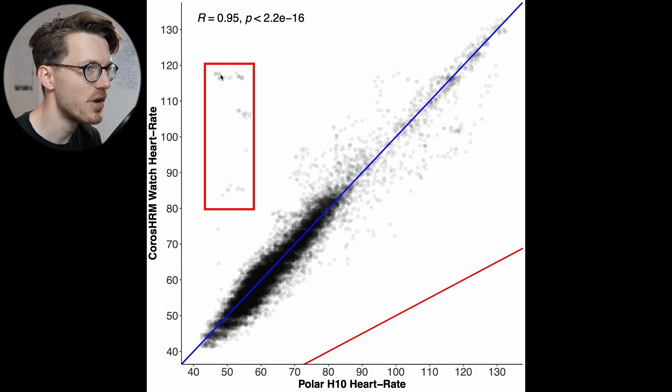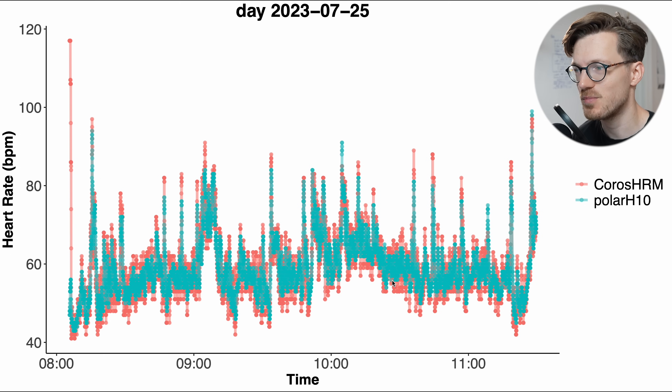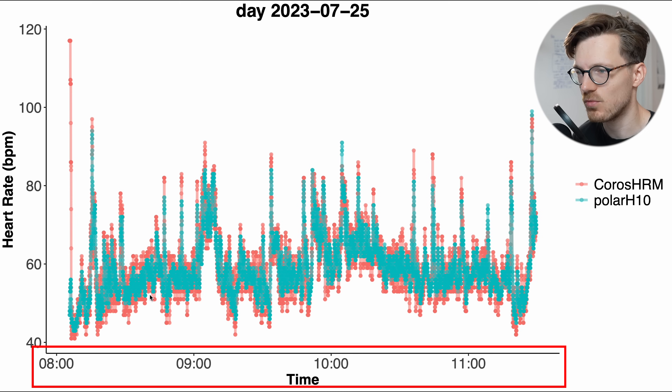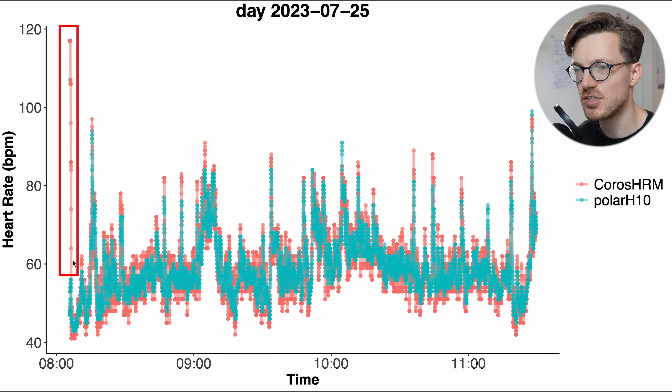Though there were some moments where the Coros heart rate monitor detected a too-high heart rate — probably double what it should have been in some instances. Still, overall the agreement is very good and the correlation at 0.95 isn't bad at all. Here you can see the results for the first part of the day, where I wore the strap for about one to three hours. There's generally good agreement between both devices, though sometimes the Coros heart rate monitor tends to pick up more extreme values.